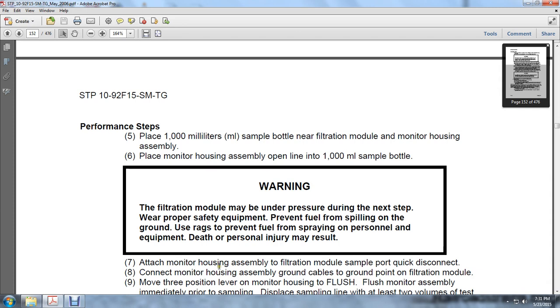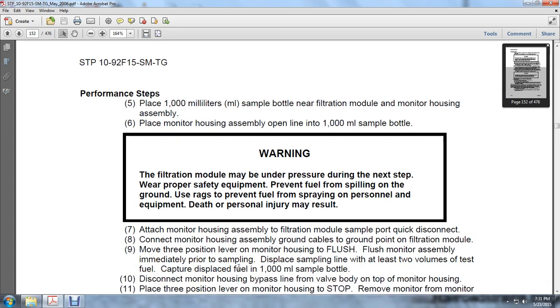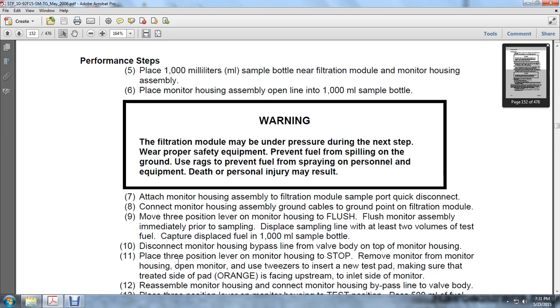Quick disconnect. Connect the monitoring housing assembly ground cable to the ground point on the filtration module. Move the 3-position lever on the monitoring housing to flush. Flush the monitoring assembly immediately prior to sampling. Displace the sample line with at least 2 volumes of test fuel. Capture the discharged fuel in the 1,000 milliliter sample bottle.